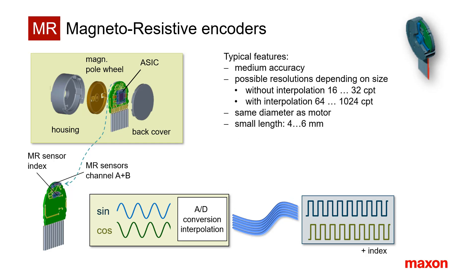The low-resolution version creates one encoder pulse per magnetic pole, simply by rectifying the sine and cosine signal. The high-resolution versions use an ASIC for signal interpolation and as a line driver. Due to the interpolation and other tolerances, the MR encoder has a lower accuracy than the optical encoder.